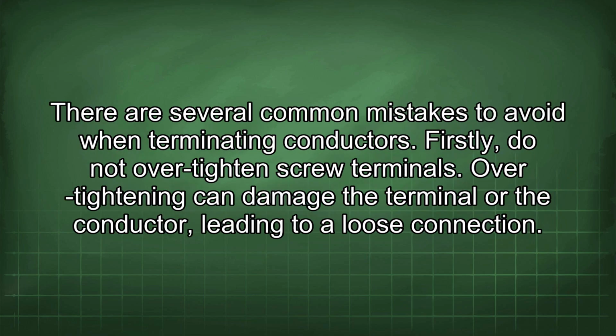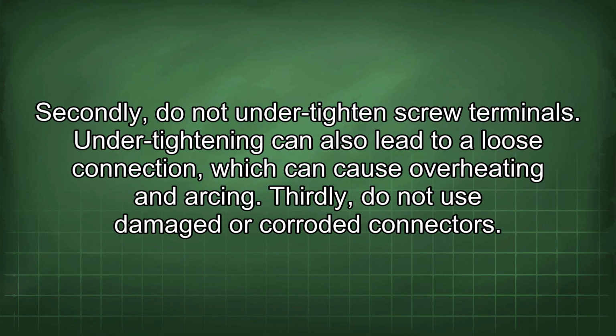There are several common mistakes to avoid when terminating conductors. Firstly, do not over-tighten screw terminals. Over-tightening can damage the terminal or the conductor, leading to a loose connection. Secondly, do not under-tighten screw terminals. Under-tightening can also lead to a loose connection, which can cause overheating and arcing.